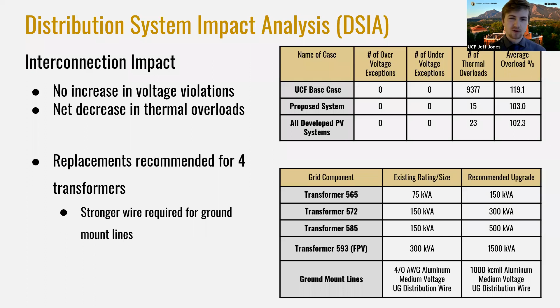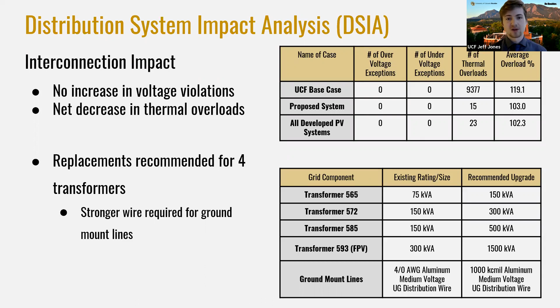The final row is just a recommendation to use a stronger type of wire for the ground mount lines that will need to be installed for the ground mount system, since they have to handle more power than anywhere else on the grid. But with these upgrades in place, we should be able to decrease thermal overloading from where it is now, so we don't anticipate any major problems with interconnecting the proposed PV systems.